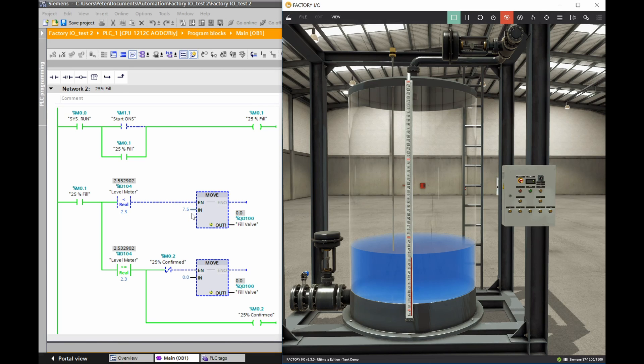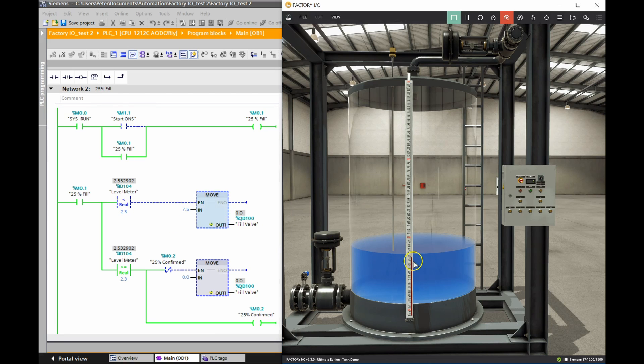I'm not doing the full 10 volts to the fill valve - the full 10 volts was too much and caused too much distortion on the water surface. I put it at 75% of that value. I set the cutoff at 2.3 rather than 2.5 because when I turn off the valve there's still some water that comes down, so I turn it off early at 23% so that it subsides at 25%. If it hasn't reached that value, send 75% to the fill valve; once it gets to 23% then shut it down.